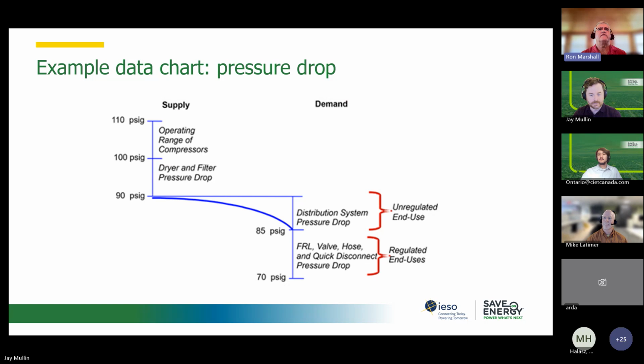You can take the readings off that chart, and you can perhaps do a chart like this. And this is from the Compressed Air Challenge Fundamentals, right? So you can see where the pressure loss is. So we can see the operating range of the compressors. That's control of the compressors. They might be loading and unloading between 100 and 110. There's pressure loss across the dryer and filter, right? Pretty significant in this case, 10 psi. That curve, that blue curve, is the pressure loss across the distribution pipework. And it's a curve because as the air gets farther and farther away, it expands, right, due to the pressure loss.